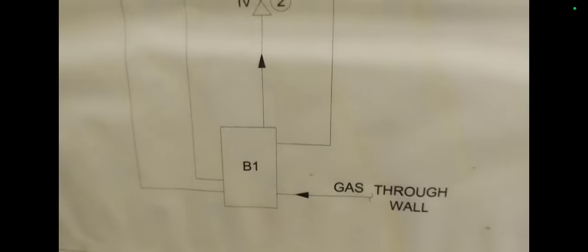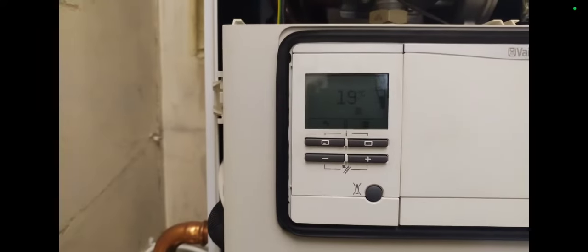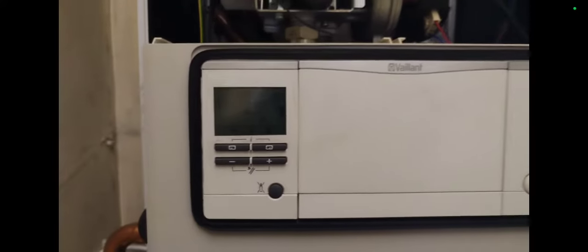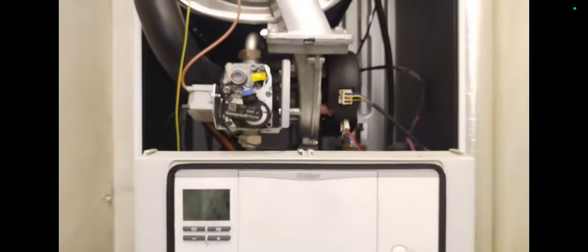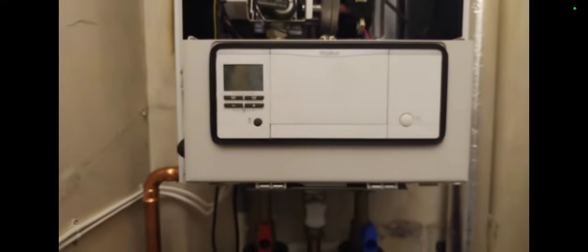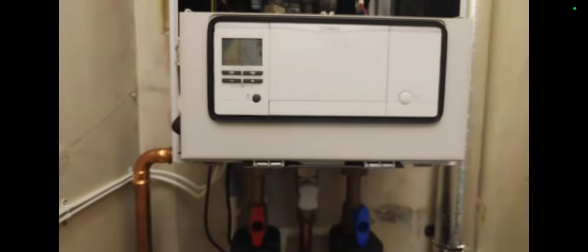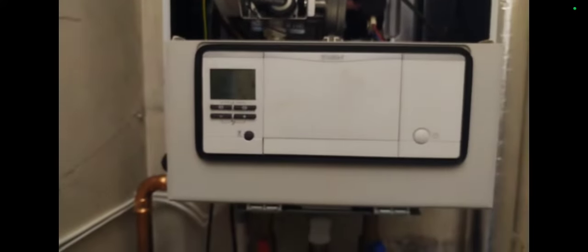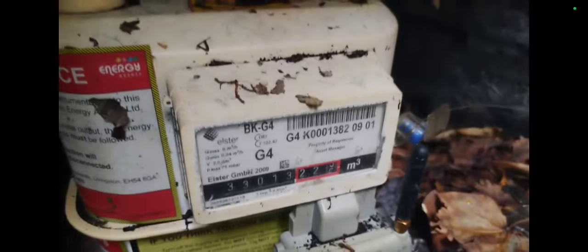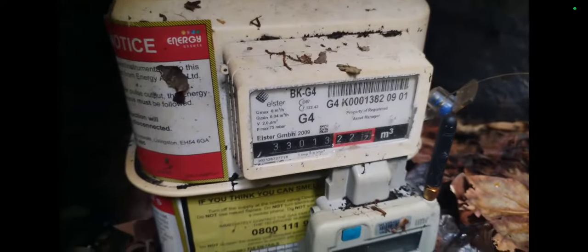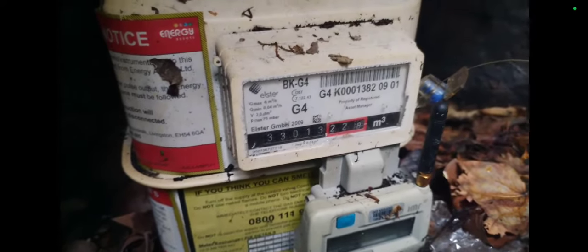The wiring diagram. Getting the boiler to come on. And then I'm going to have to get into high and low soon on the installer mode. So we know the boiler works. That was my first test to just ensure that the boiler was working. And then now I'm just carrying out a visual.